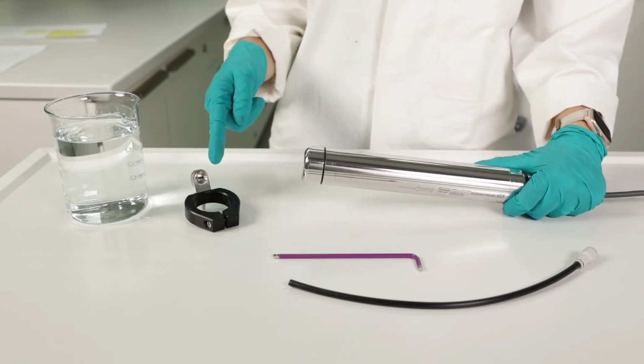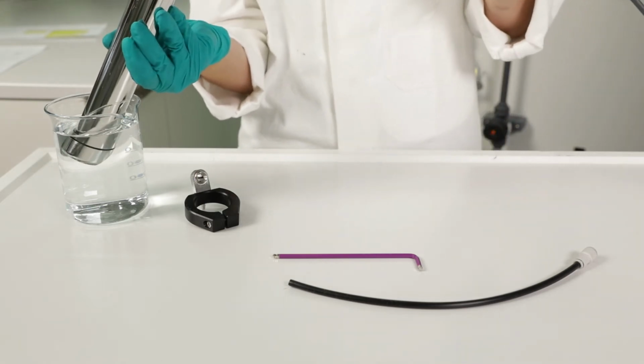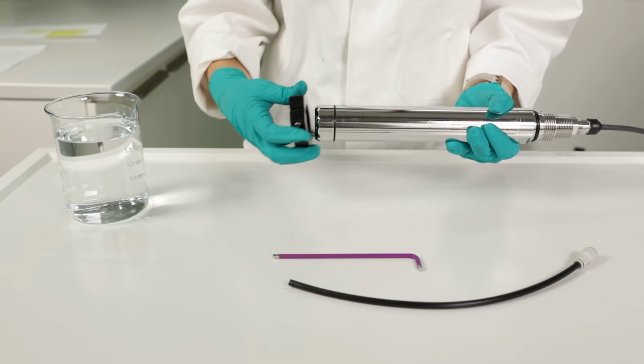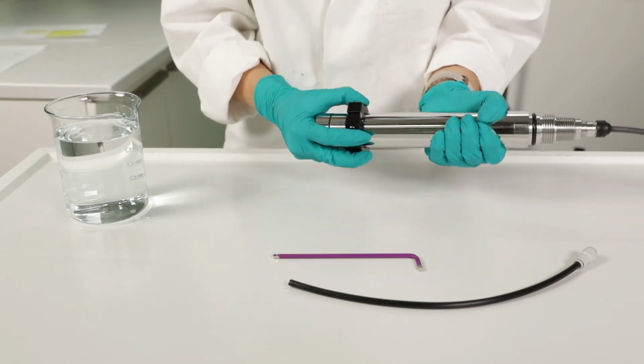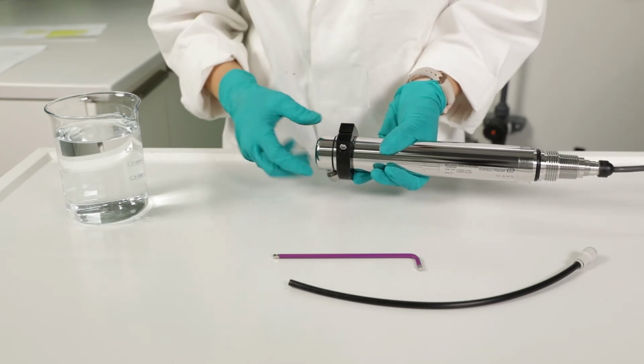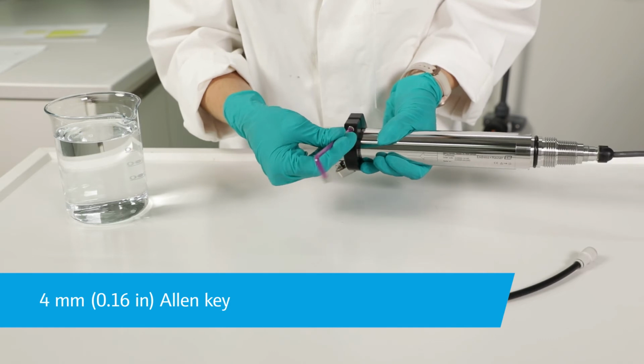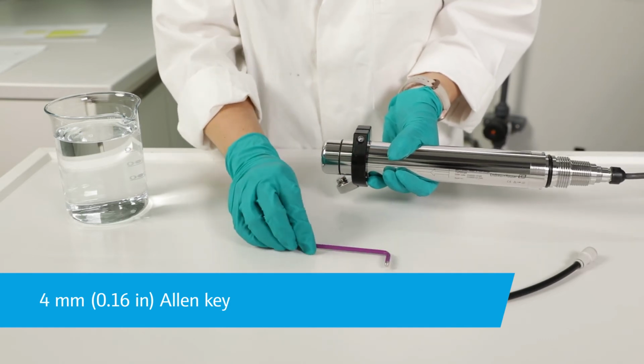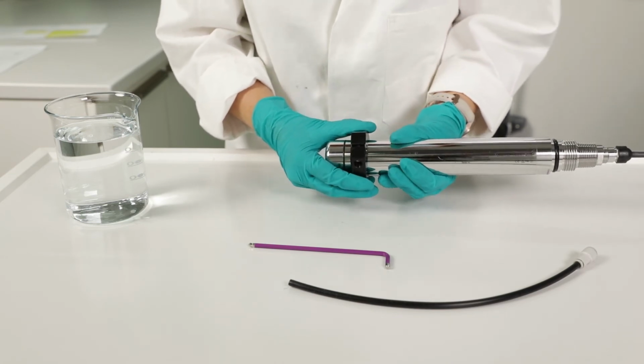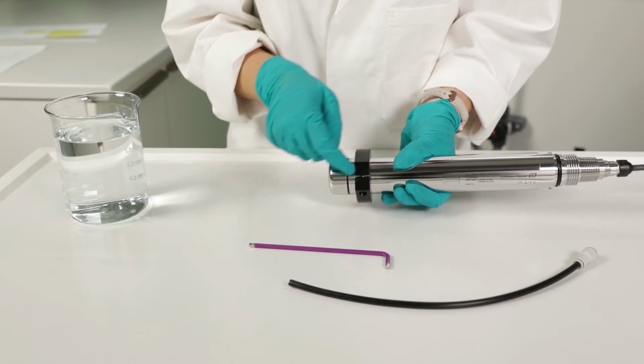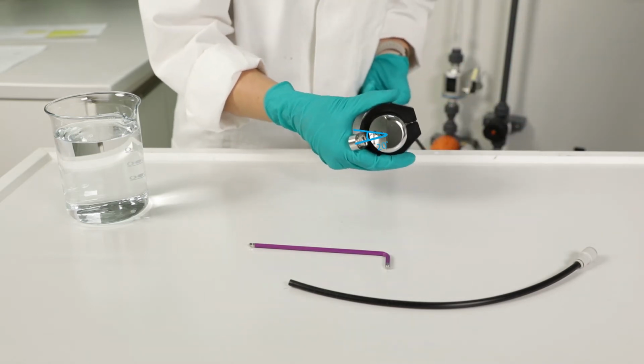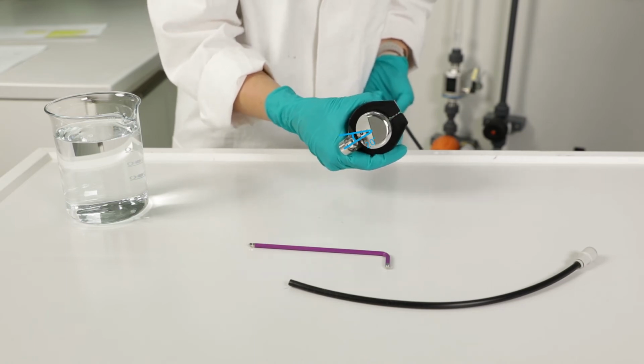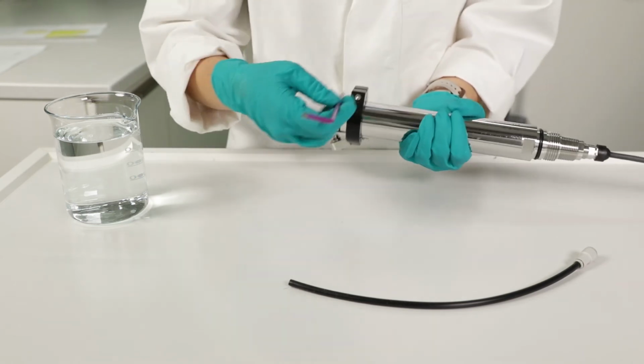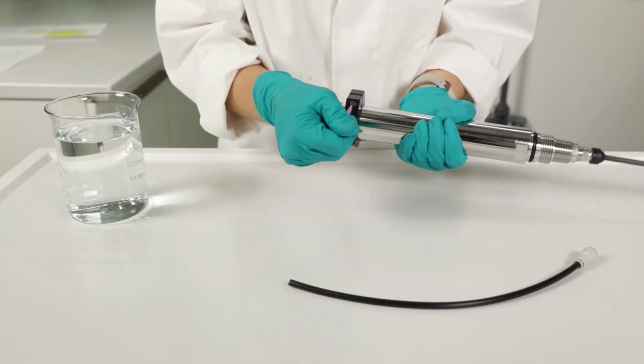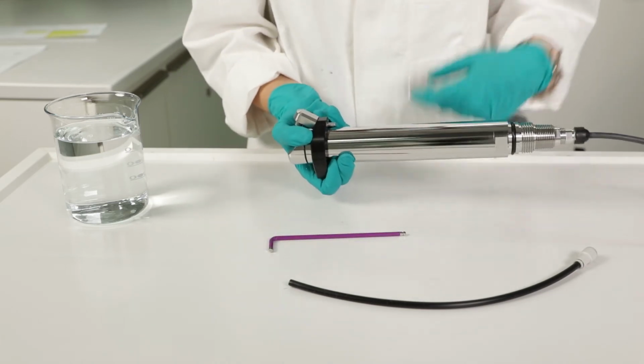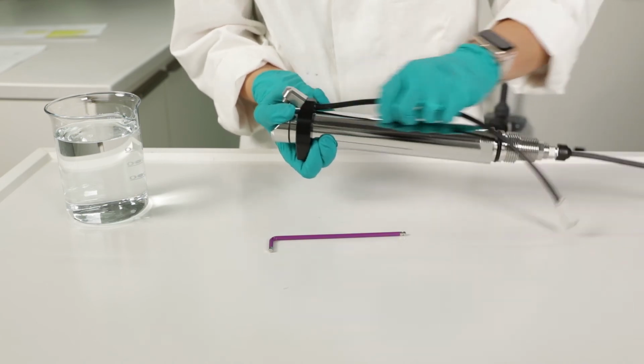At first, fit the compressed air cleaning system on the sensor. Wet the sensor head in order to simplify the installation. Then position the securing ring for the compressed air cleaning system between these two installation marks. Use an Allen key to tighten the securing screw of the compressed air cleaning system slightly so that the unit can still be rotated. Turn it until the slit on the black ring is on this vertical installation mark. In this way, the nozzle is offset by 20 degrees when blowing air at the optical windows. Then tighten the securing screw and fit your compressed air hose on the 8 mm hose adapter, or if you have a 6 mm hose, remove the adapter and connect it directly to the 6 mm hose barb.